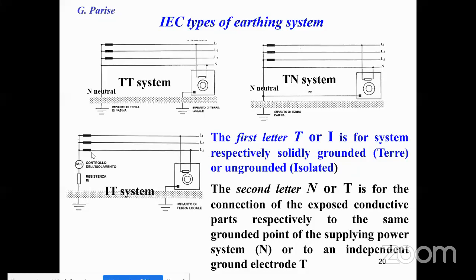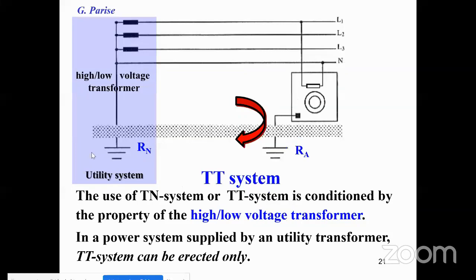The second letter, N or T, is for the connection of the exposed conductive part, respectively, to the same ground point of the supplying power system or to an independent ground electrode. I will show this in the next slide. So let me show the case of the TT system. One time, an American technical person asked me why TT, why TN?